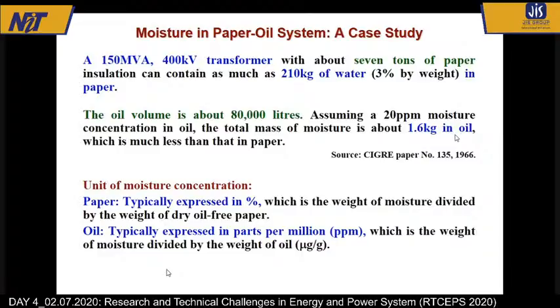Now, that's what I want to highlight to all of you, that 3% by weight and 20 parts per million is not very bad, but it's warning level. But look at that, 210 kilo of water will be in paper and only 1.6 kilo in oil. That's the real situation in a practical transformer. And these 210 kilo of water will damage further the paper insulation. To replace the 7 tons of paper insulation, practically it is half of the transformer cost.